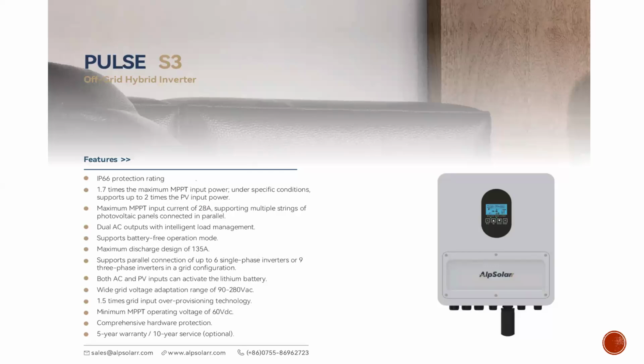It has a minimum MPPT operating voltage of 60 VDC. This is one of the most beautiful features I love about this inverter, that it needs just 60 volts to start working early in the morning. So early in the morning while the sun is not yet out, so far the panels can generate up to about 60 volts, the inverter starts working. And even late in the evening, so far you can still get up to 60 volts, the inverter is already activated through the PV.